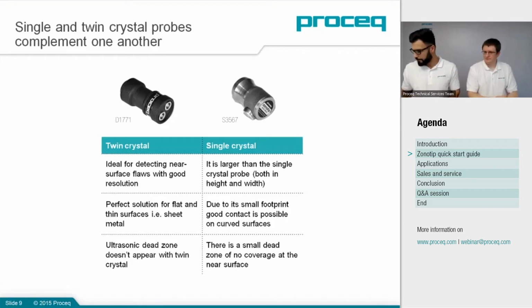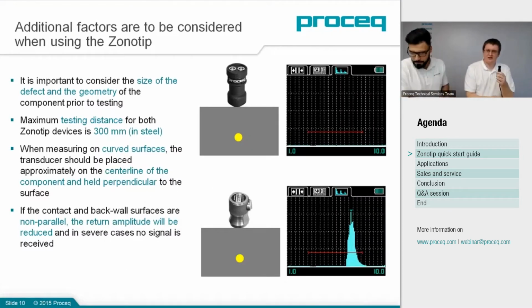Fantastic. Thanks, Chris. So yes, now I'll mention the effect of frequency. The 4 megahertz transducer and the 2 megahertz transducer we've got. The 4 megahertz higher frequency won't travel as far in the component, but it does offer better resolution. So you've got to balance it out really of which we want to choose. If you want to go down deep into a component, use the lower frequency, and vice versa for the higher frequency. You can see the example here that sometimes because of material scatter, you might not be able to reach the target as shown by the twin crystal there. If you drop the frequency down, it can penetrate more, so that's good.